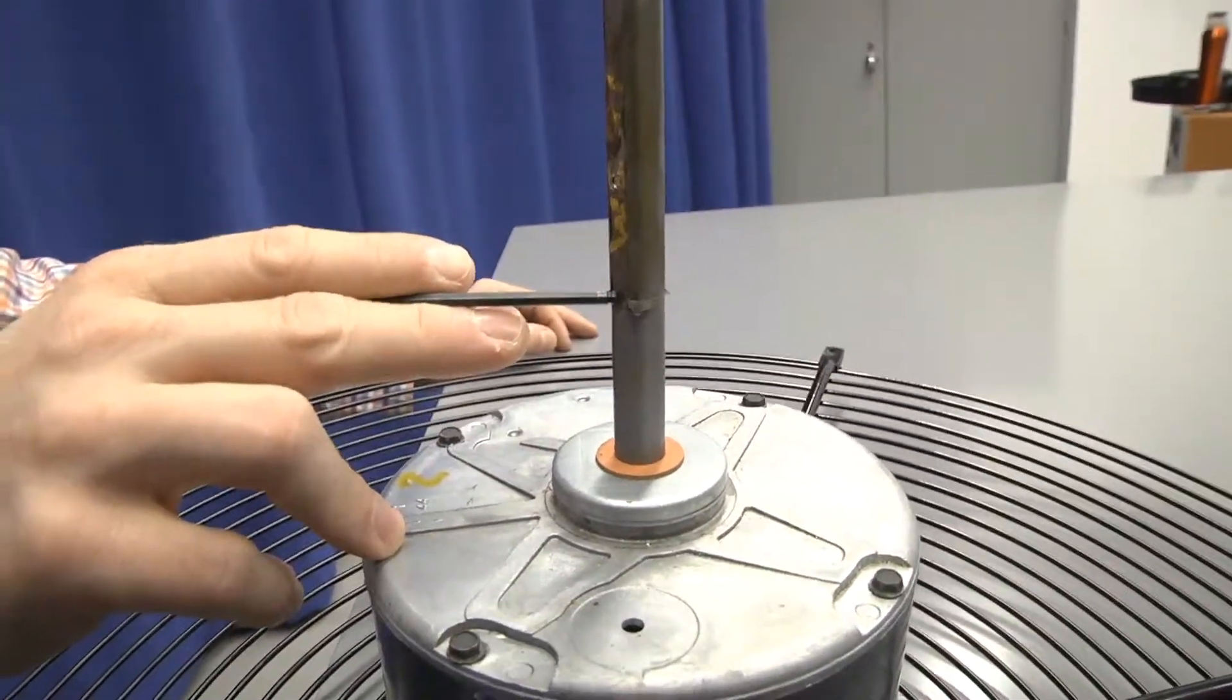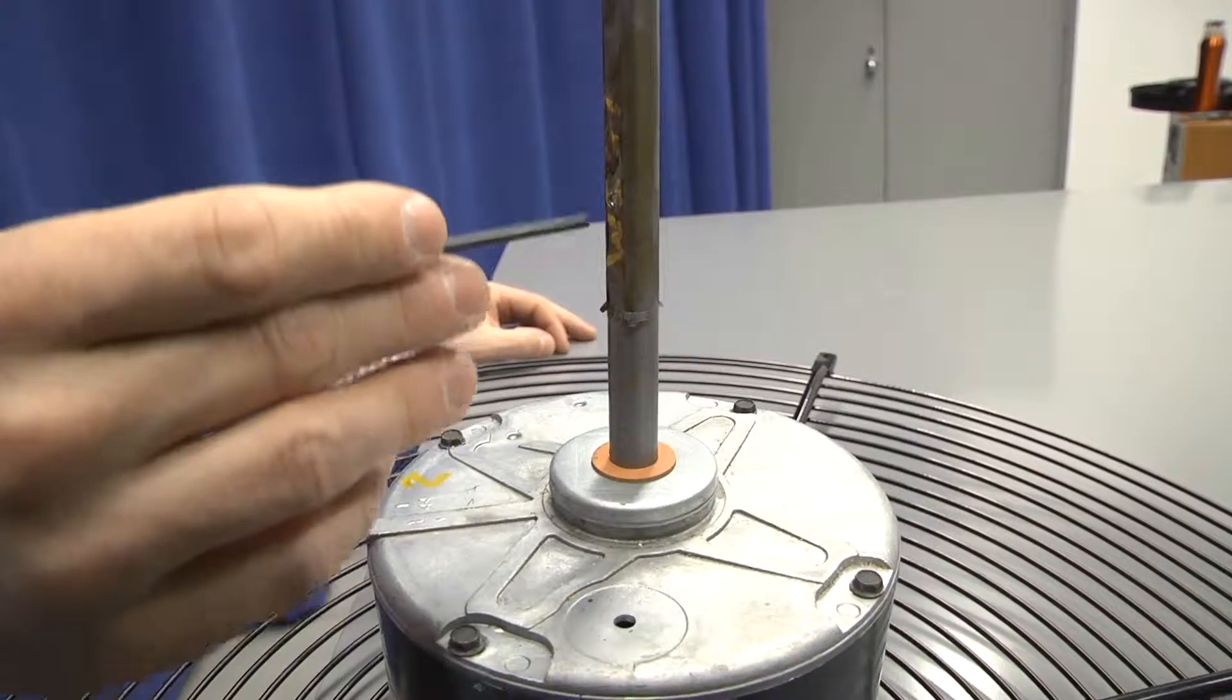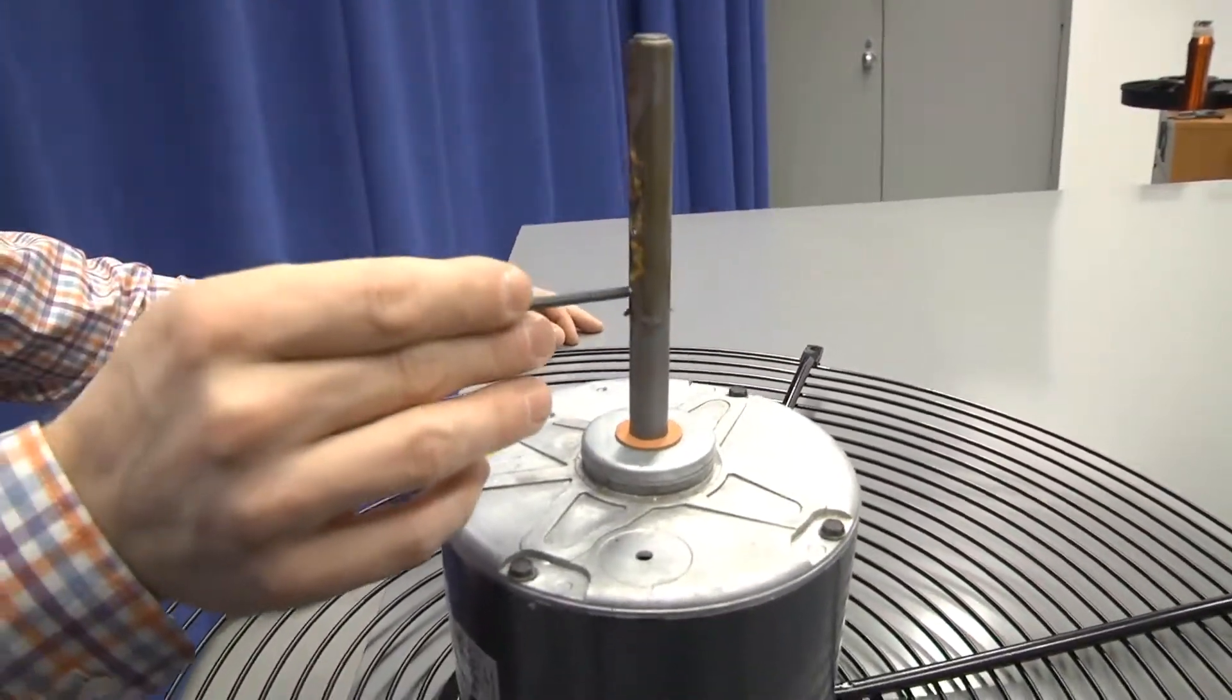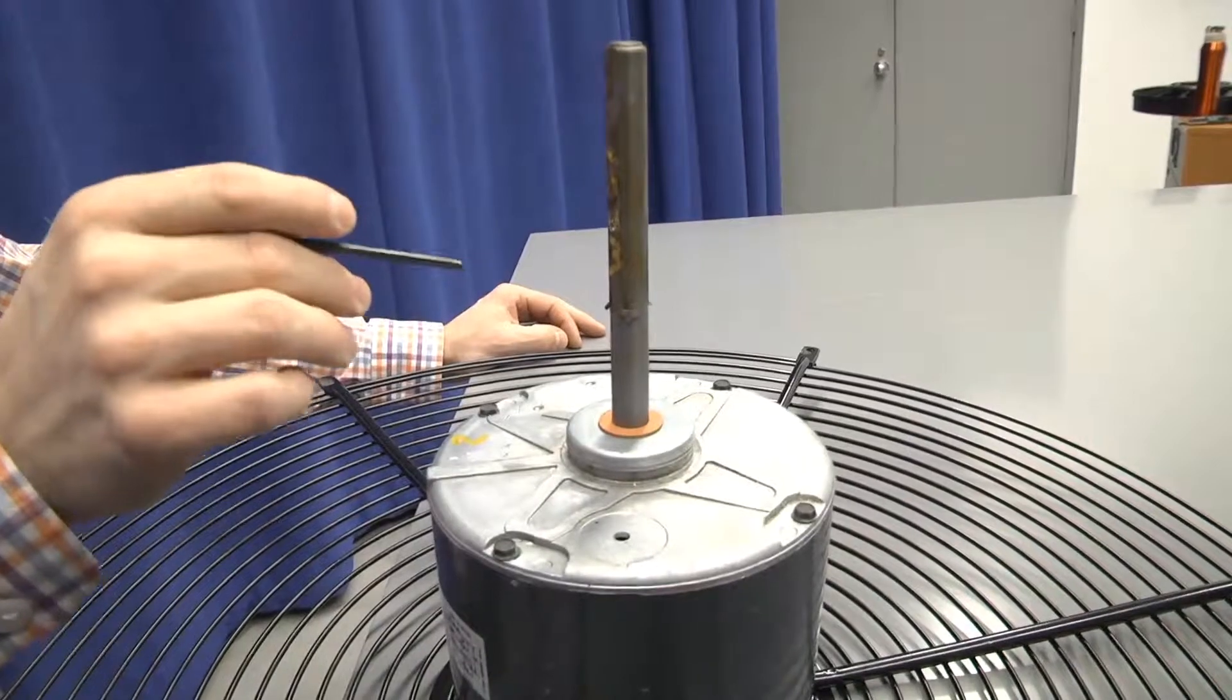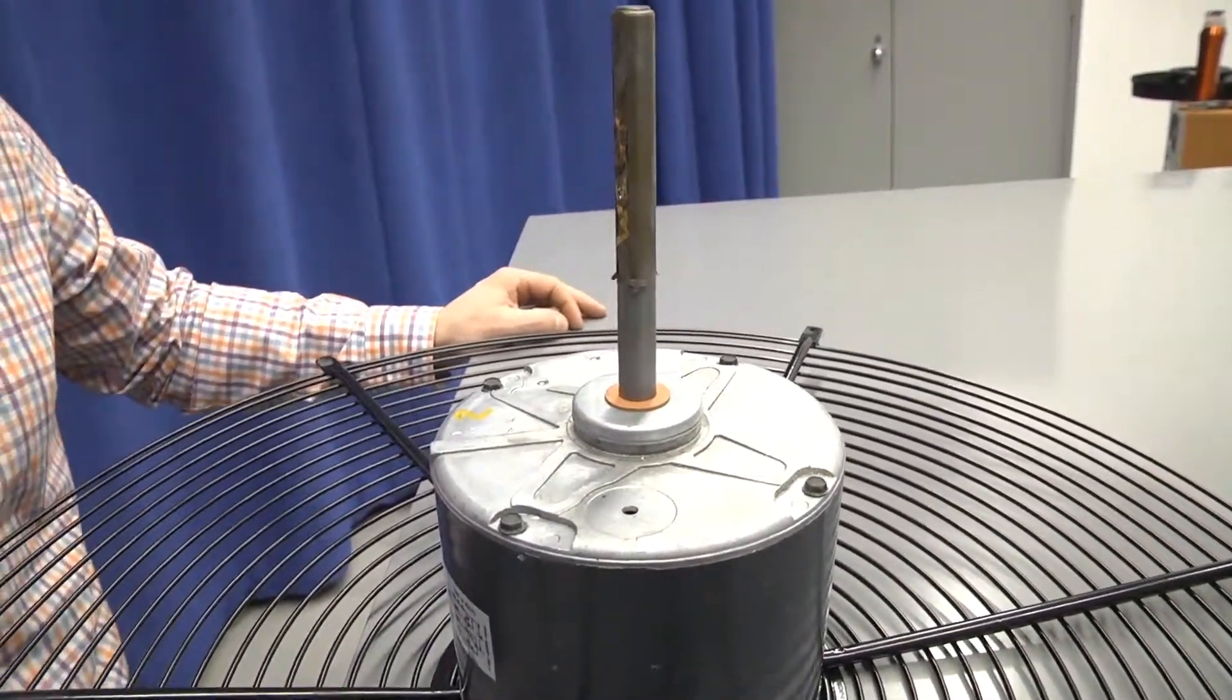So when you put the fan back on, the D is going to ride down the flat portion of the shaft and then bottom out on that ridge there. And that sets it in the correct axial position in the orifice.